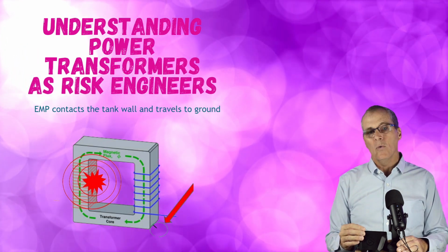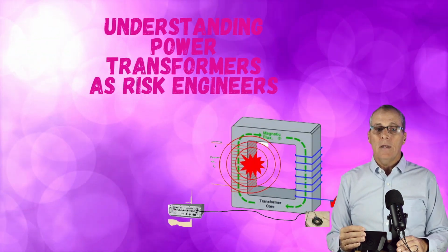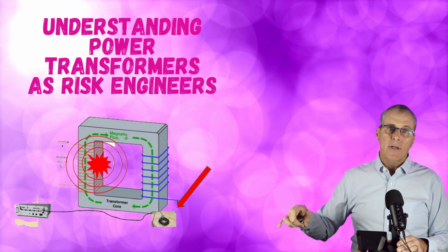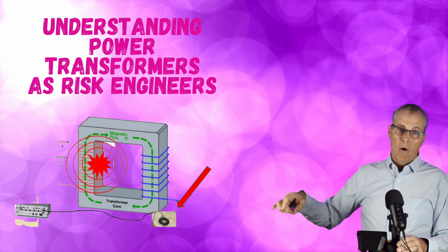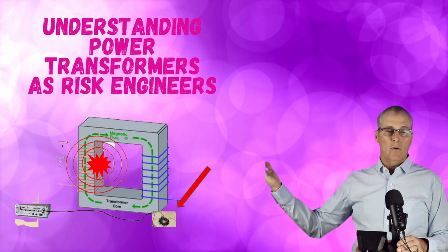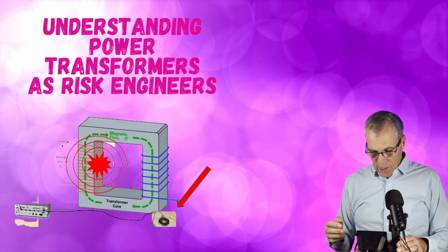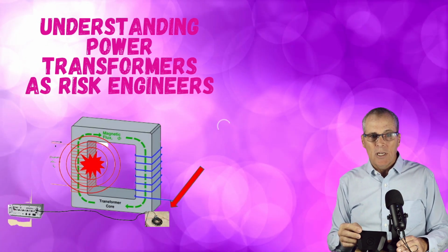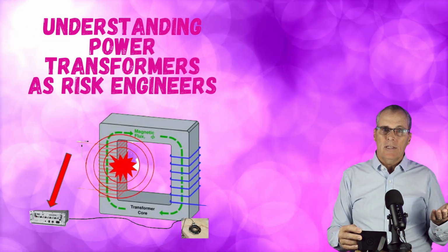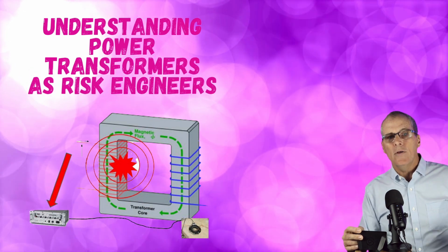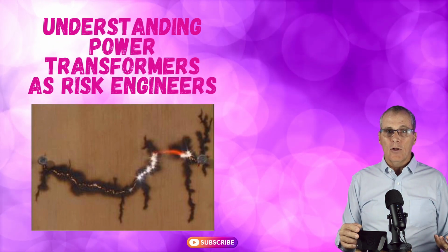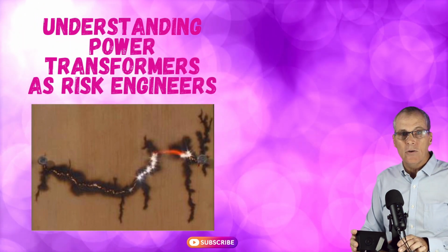So we've got something going on with EMP that if we hook up a coupler, basically a magnetic coupling on that ground clamp, we can read the EMP going through it while the transformer's in service, full load, full power. Then the machine analyzes the information and gives us a great readout so we can figure out: do we have partial discharge? Is it a problem? Is it about to cause a failure?